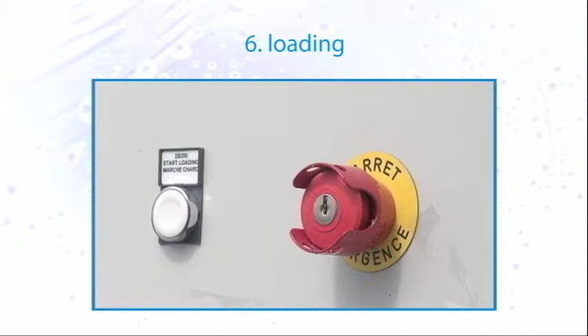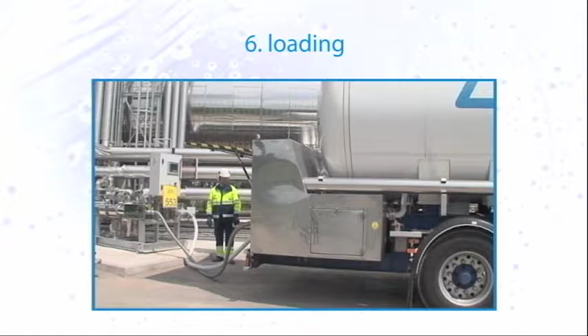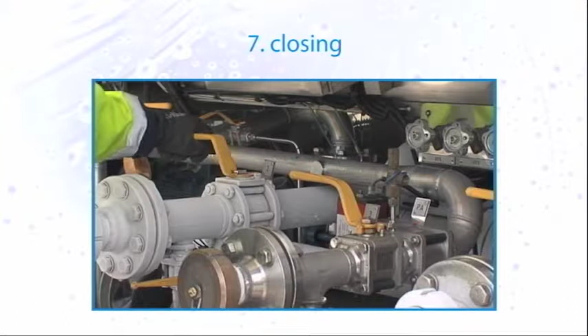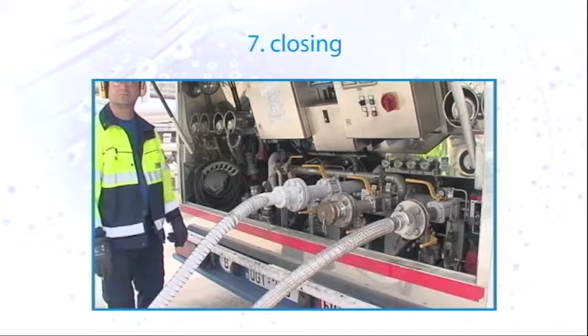If you want to interrupt the loading cycle, this is possible by pressing the emergency stop button. During loading, always remain in the vicinity of your lorry. When loading is finished, close the gas and liquid valves on the lorry. Warning: you may never load more than the requested quantity.